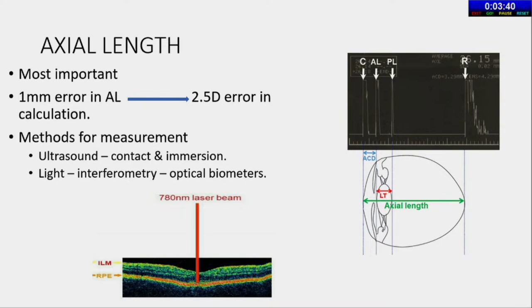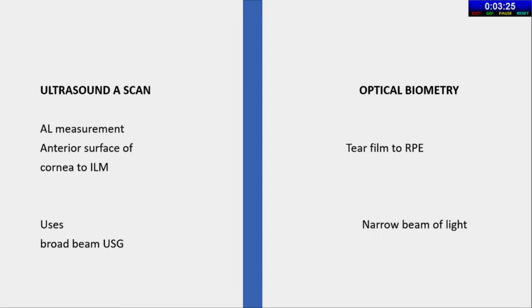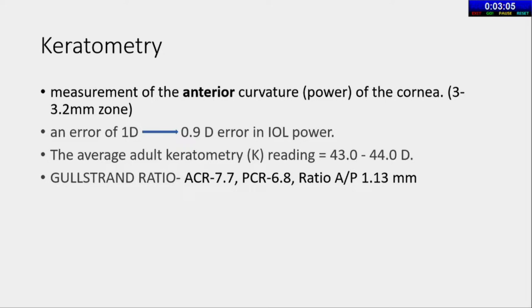The important methods of axial length measurement are ultrasound (contact or immersion) and optical interferometry via optical biometers. In ultrasound A-scan, the axial measurement is from the anterior surface of the cornea to the internal limiting membrane. In optical biometry, it is from the tear film to the retinal pigment epithelium. Keratometry measures the central 3 to 3.2 mm zone, and an error of 1 diopter causes approximately 0.9 diopter error in IOL power, with average readings of 43 to 44 diopters.